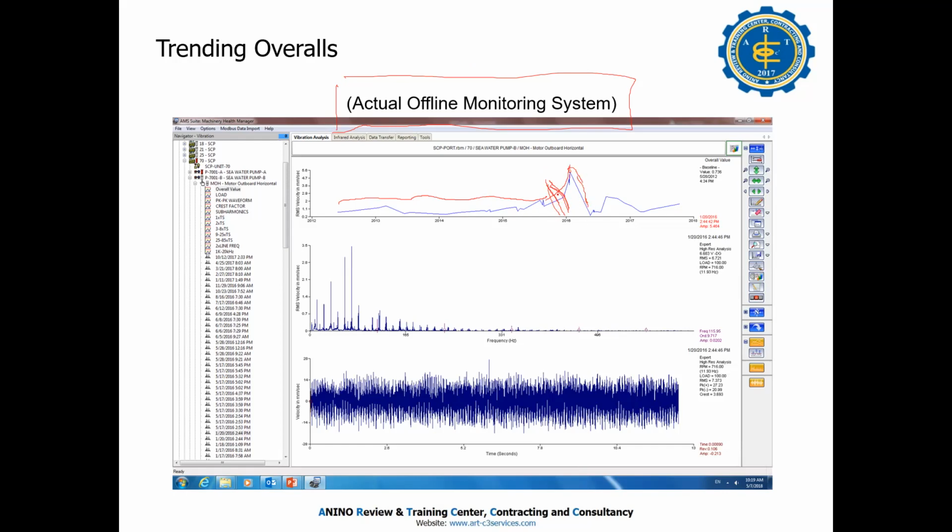But they did not see what happened. They did not say that we will shut down, even though the vibration goes up here. Only at this time did they say okay, shut down. When we get this vibration reading, we shut down immediately because the vibration is very high. So we are safe as employees, safe in our work. That's important.